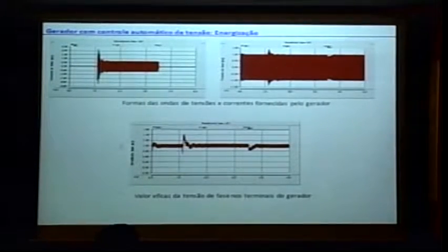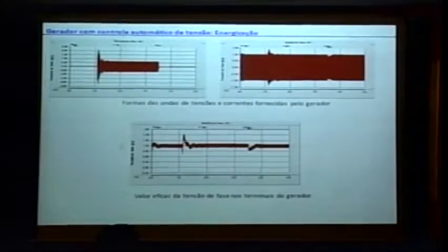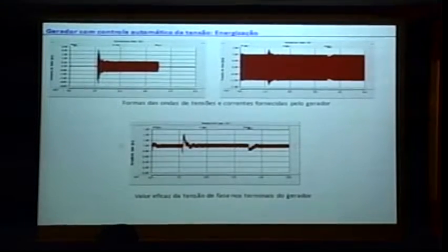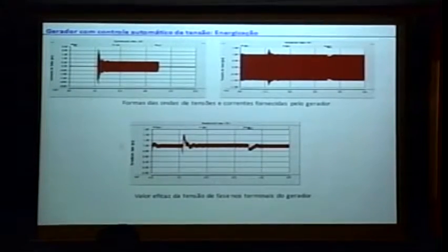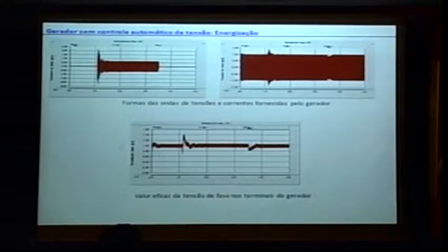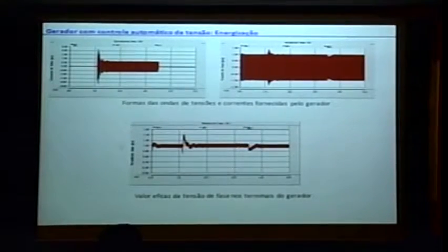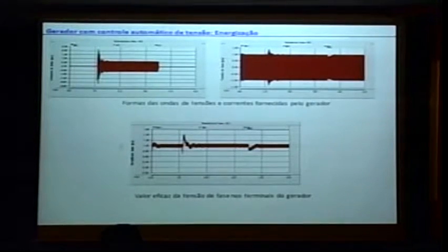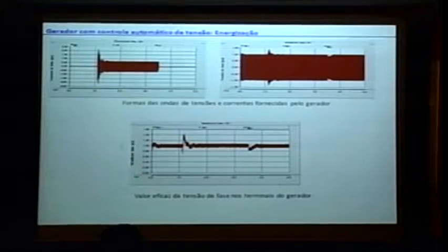When you do the energization, excessive reactive onto the machine, so the voltage goes up, but the AVR can regulate it, bring the tension back to the reference of 1 pu. When you have the disconnection, now you don't have a field in the machine, the voltage falls and the AVR works once again to bring the voltage to 1 pu. Here is no load, here is energizing the network. Here are the voltage values in RMS.